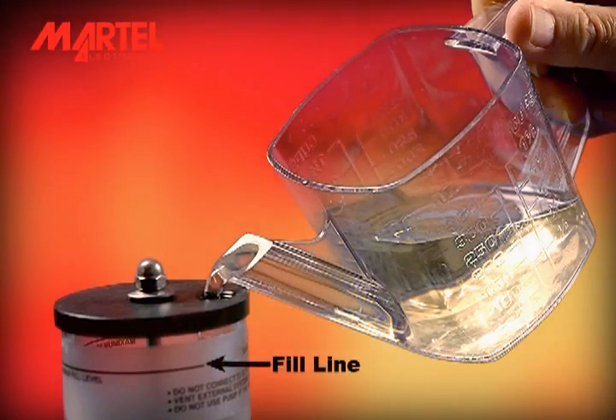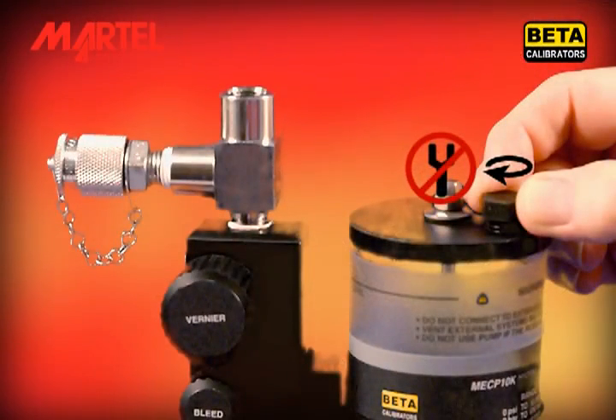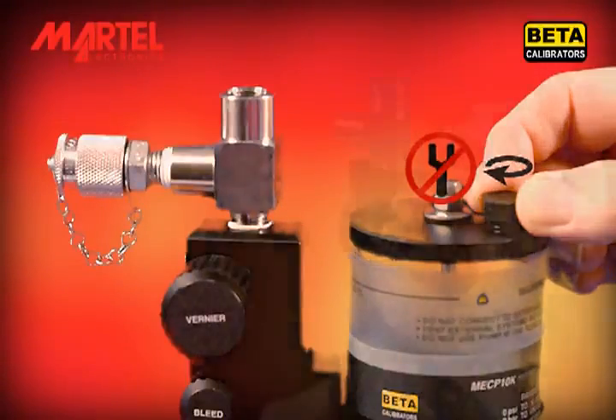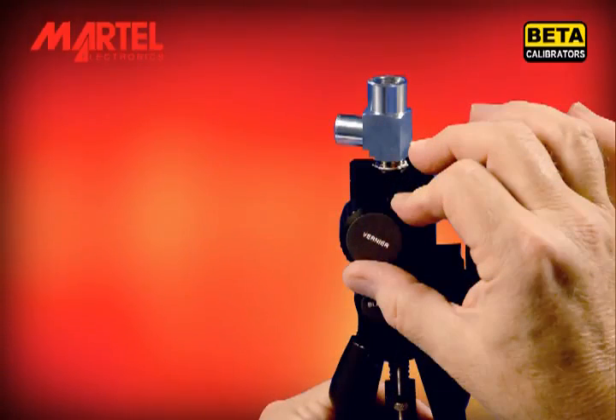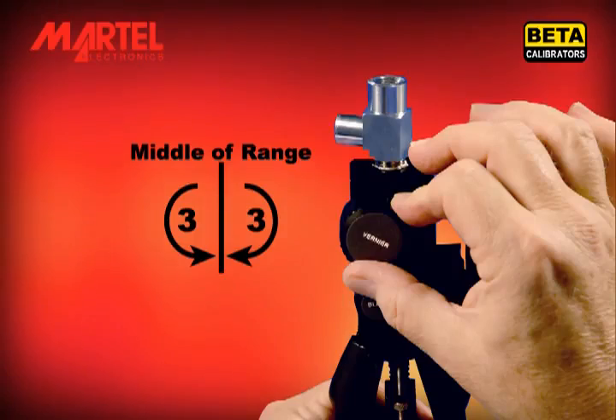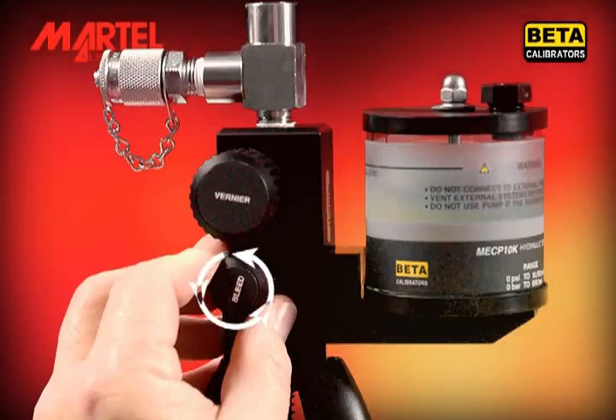Do not overfill the reservoir. Replace the filler cap finger tight. Do not use any tools to tighten the cap. Adjust the vernier knob to the middle of its range, that is, about 3 full revolutions from either end of the range. Open the bleed valve fully.